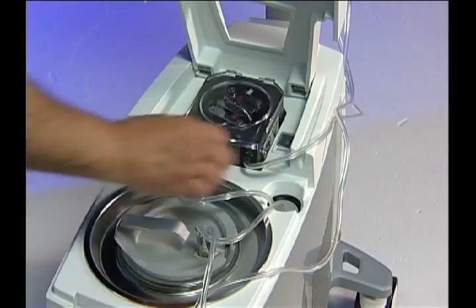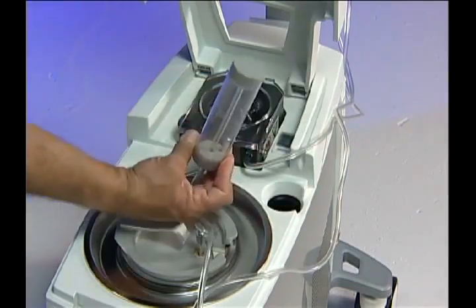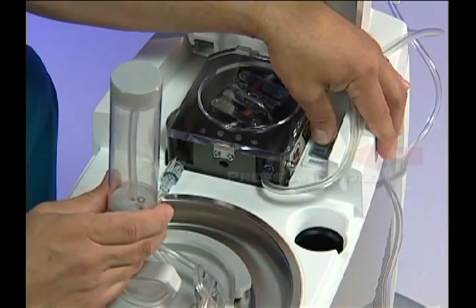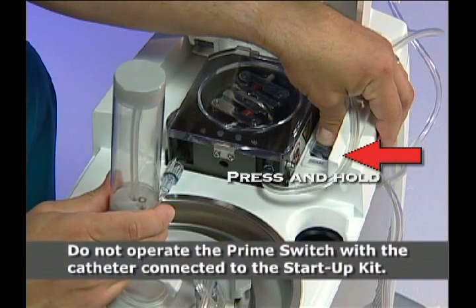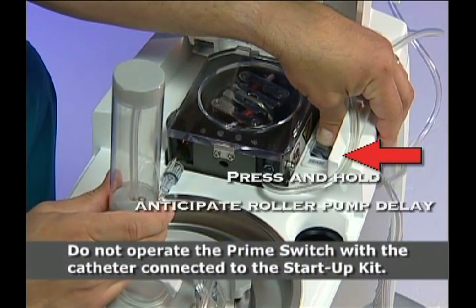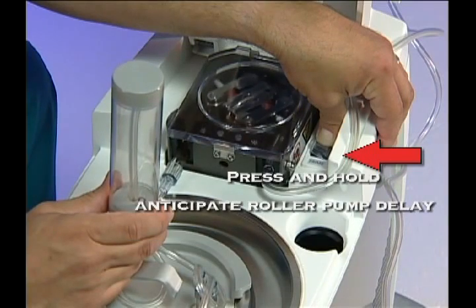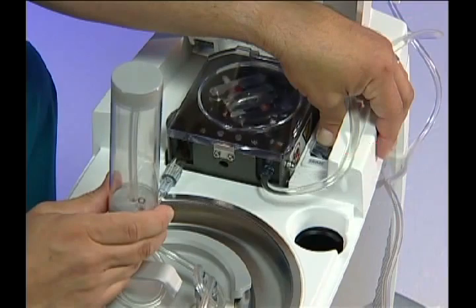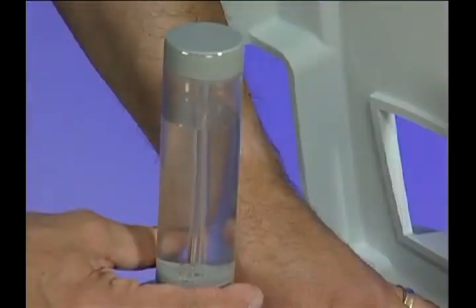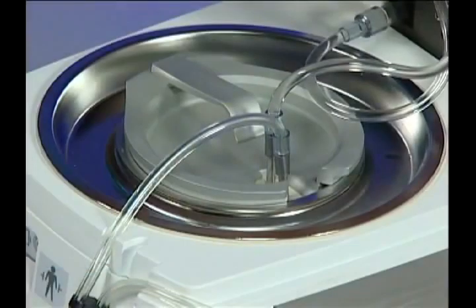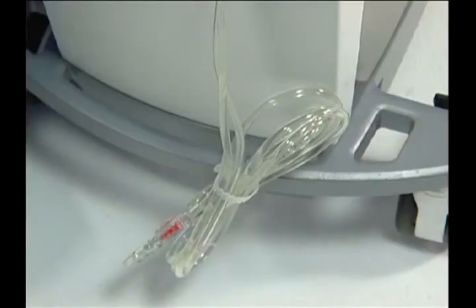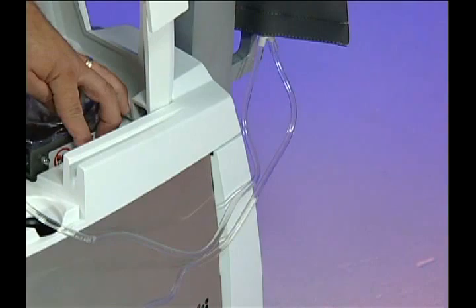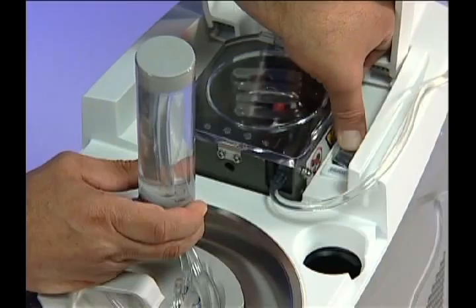Next, remove the air trap and hold it upside down. Press and hold the prime switch. In a few seconds, the pump will begin to turn. As it slowly rotates, watch the saline move through the tubing. It will take about 2 minutes to fill both the air trap and the entire length of tubing. Once priming is complete, you may release the prime switch.